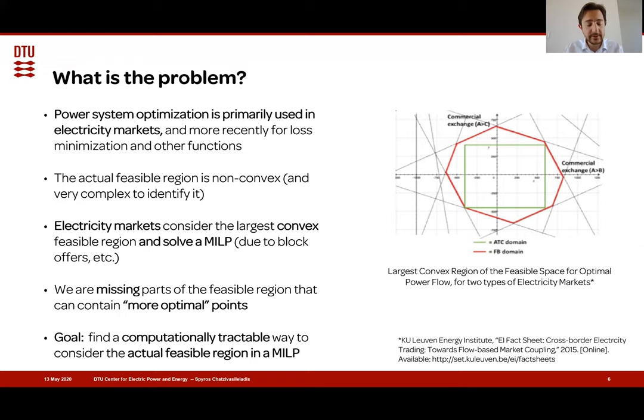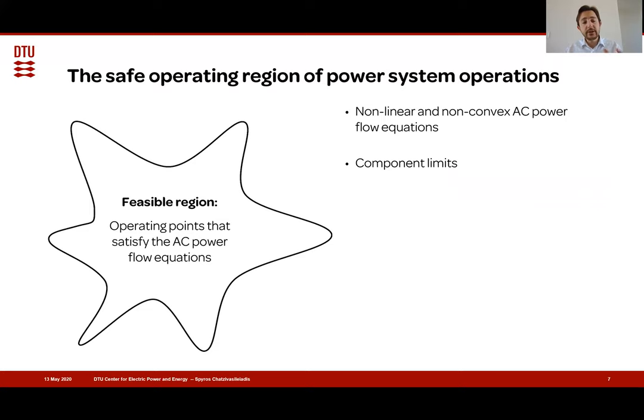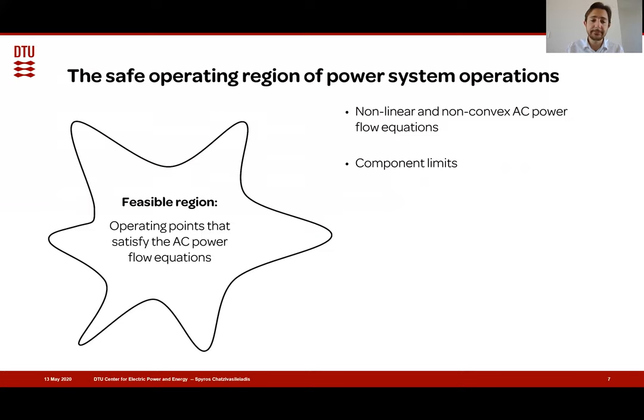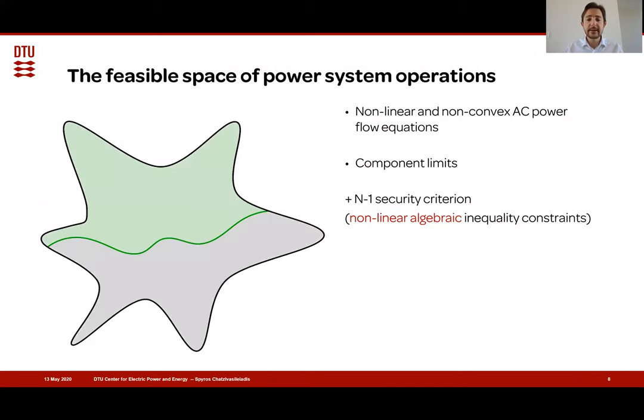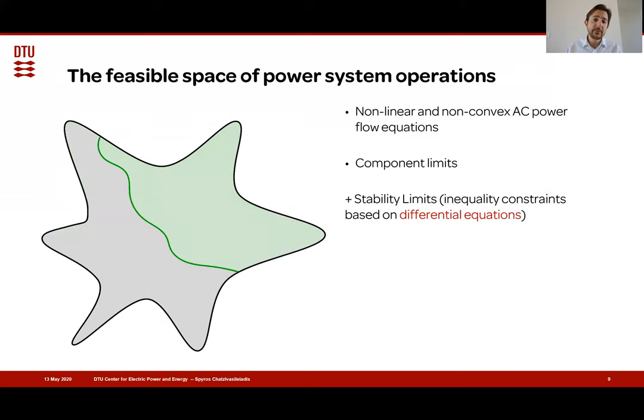The original feasible region is characterized by operating points that satisfy the AC power flow equations — quadratic constraints — making this feasible region a nonlinear non-convex set. Adding component limits further constrains it. On top of that, we have to limit this feasible region by security criteria. For example, the N-1 security criteria, characterized by sets of nonlinear algebraic inequality constraints, limits this region to a sub-region. At the same time, stability constraints limit this feasible region to another sub-region.